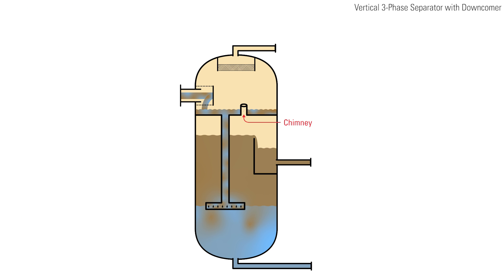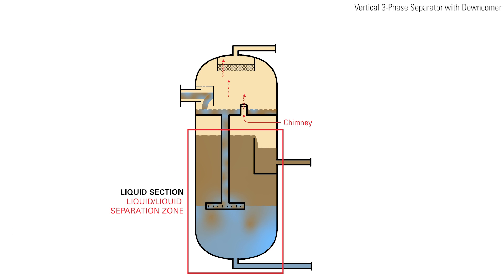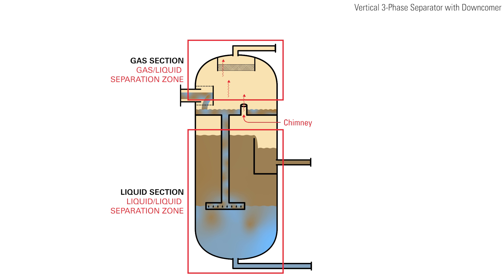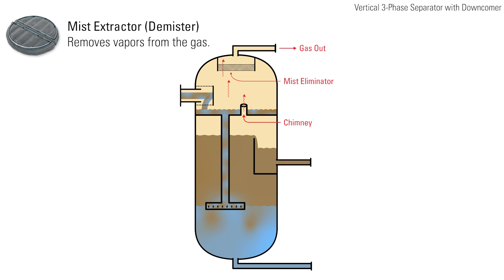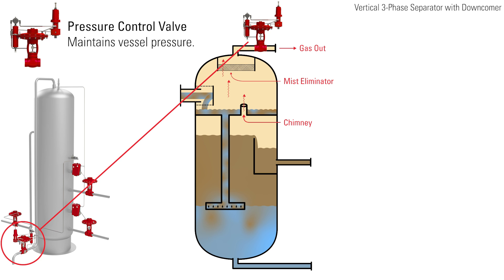A chimney equalizes gas pressure between the lower section of the vessel — the liquid-liquid separation zone — and the gas section, the gas-liquid separation zone. The gas exits through a mist extractor to a back pressure control valve, which maintains constant vessel pressure.